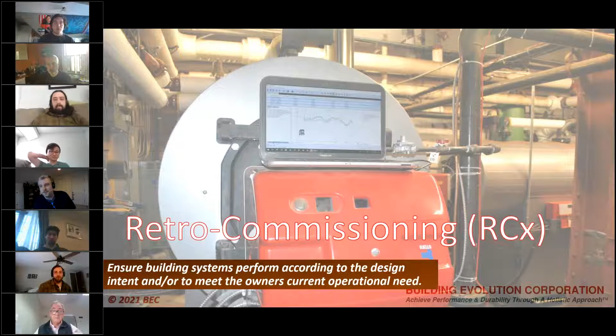Here's an example: a boiler plant with two large boilers with enough capacity for the building, actually 3 buildings attached together, an old mill converted to multifamily. Yet one of the 3 buildings isn't getting enough heat on cold days. So what's the problem? We go down to take a look and figure out if it's an enclosure issue, a boiler issue, or something else. We bring out our data loggers.